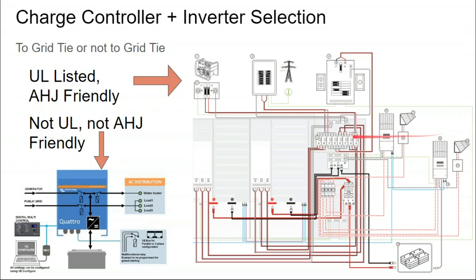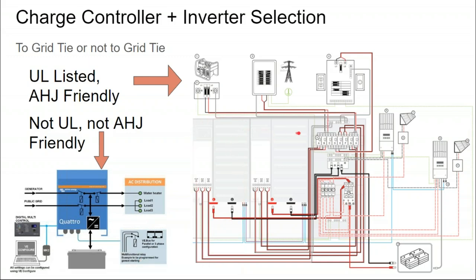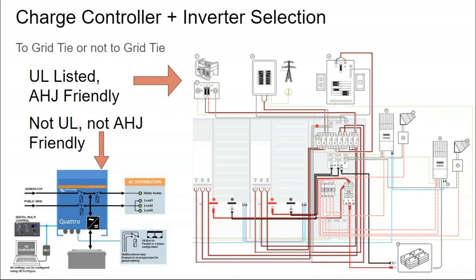Here's a Schneider system on the right, where you could just use this inverter by itself to run a small house. Or you can add another one and parallel them together, and there's an assembly block, a service panel provided by the manufacturer that, despite the atrocious cost, ends up being the best option for hooking these things up.